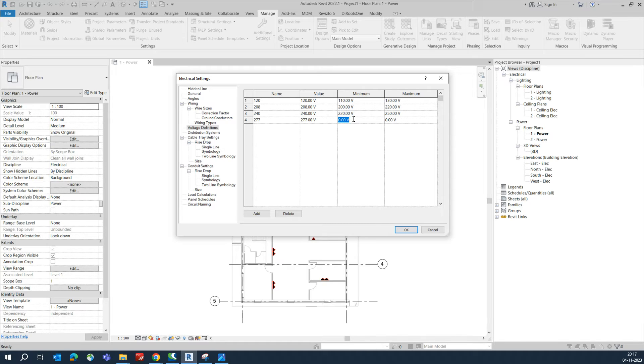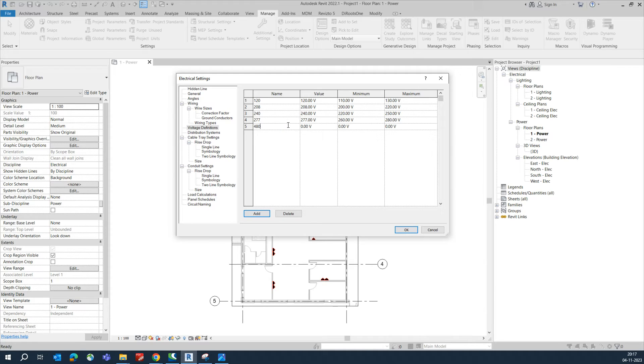For 277V, set the minimum to 260 and the maximum to 280. Then add 480V with a minimum of 460 and a maximum of 490. You can add as many voltage definitions as needed per your standards.